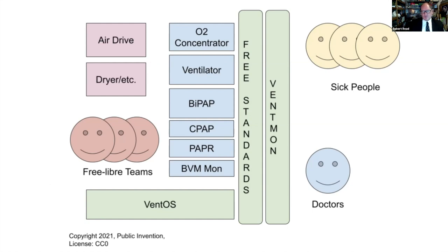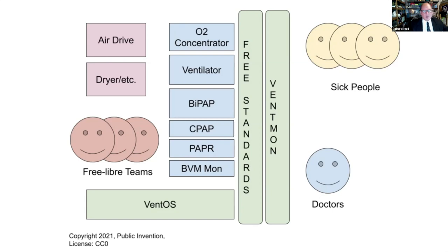By defining standards for the representation of quality, performance data, and test data — which is done with the Ventmon, designed by Ben Coombs with the help of Lauria Clark — this nice little box that several projects are already using measures pressure, flow, temperature, humidity, etc. It sends data live to a data cloud to support telemedicine and cooperation over the Internet. You can build all of these machines with synergy, and that's really what we're aiming for.